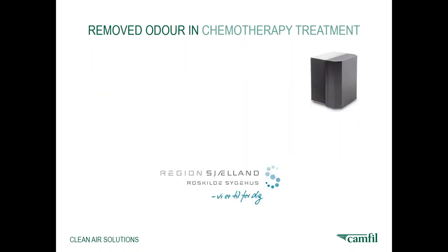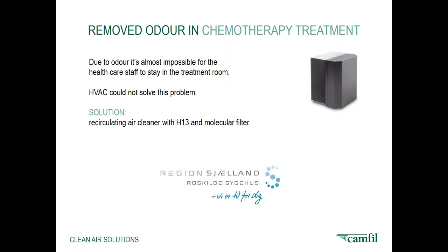In this slide, we want to show how it's possible to remove odor in hospital. And in this specific case, we removed odor in chemotherapy treatment rooms at Roskilde Hospital in Denmark. It's well known that chemotherapy patients after transplantation of stem cells for regenerating the bone marrow, in the following days give off a very strong and unpleasant smell, which makes it almost impossible for the healthcare staff to stay in the treatment room. HVAC could not solve this problem.